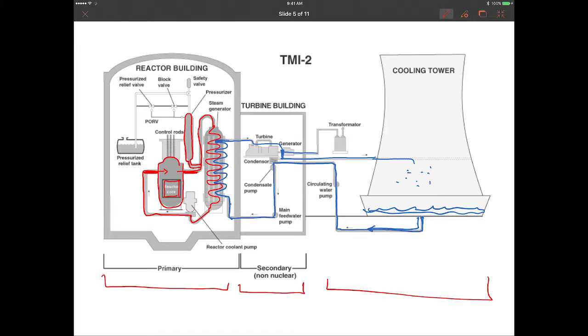So this pressurizer allows you to help control water temperature by allowing the primary water to move through the volume of this pressurizer. As water gets hotter, it has nowhere to go, so it will fall into this pressurizer area. And this is important because, as a closed system, and we'll see what happened with the Three Mile Island incident, this was really a way to help control what happens in the primary system.